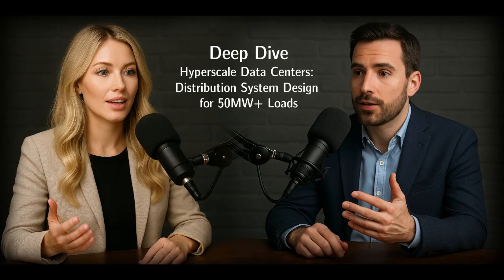It can work sometimes for smaller enterprise data centers, maybe 5 to 15 megawatts, or things like edge computing facilities, especially if there's already spare capacity on an existing feeder, or maybe if the customer is okay with standard distribution reliability.